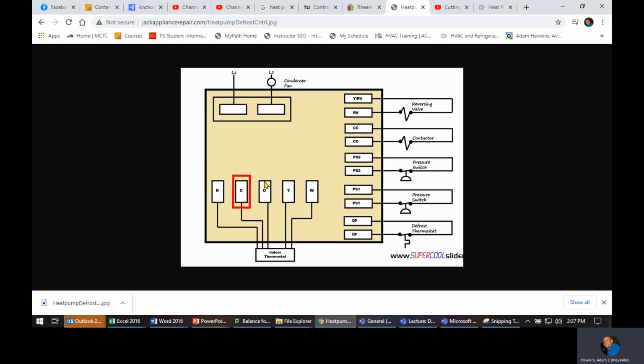So it's calling for Y the whole time. So we're calling for Y, we're calling for orange to be in the heating position. We're not calling for white right now. That's what the stat's doing. But the board, once it decides it needs to defrost, can reverse this reversing valve on its own. It can also control the contactor. It has pressure switches.